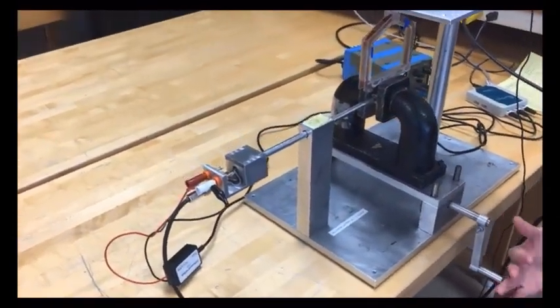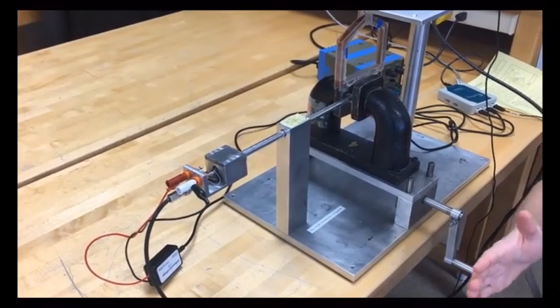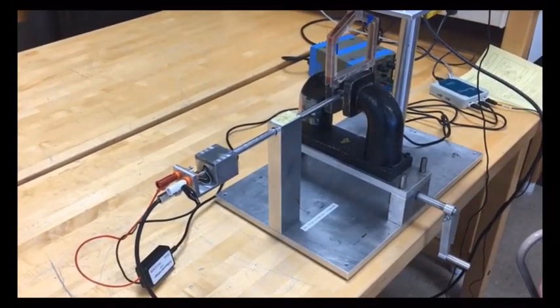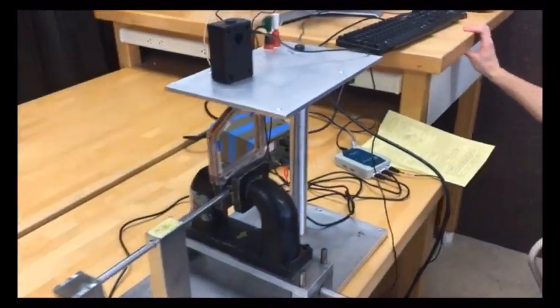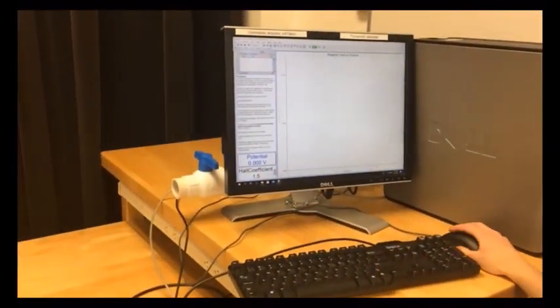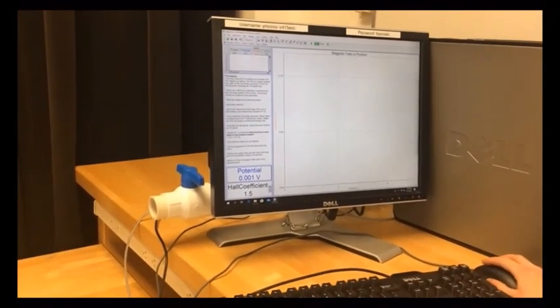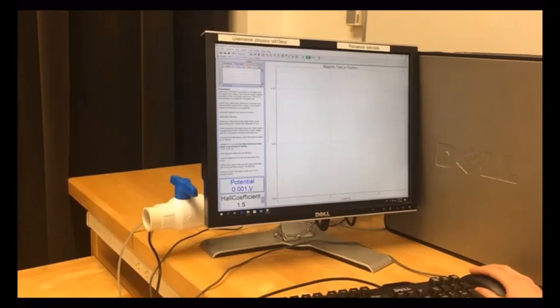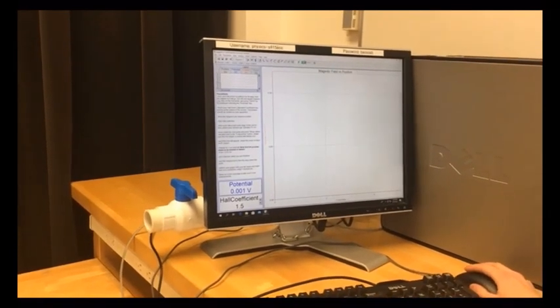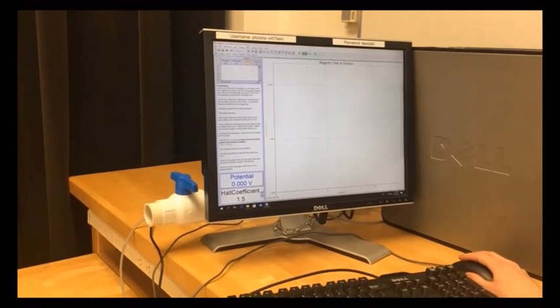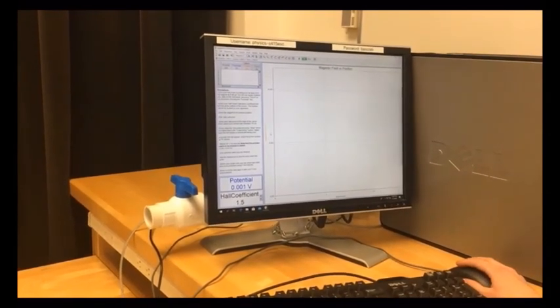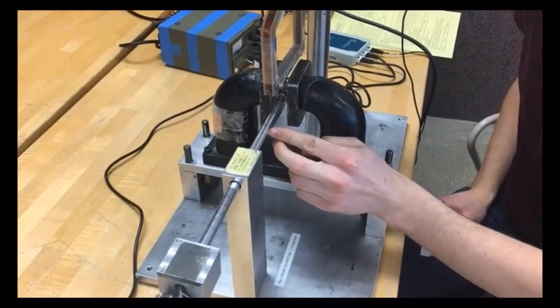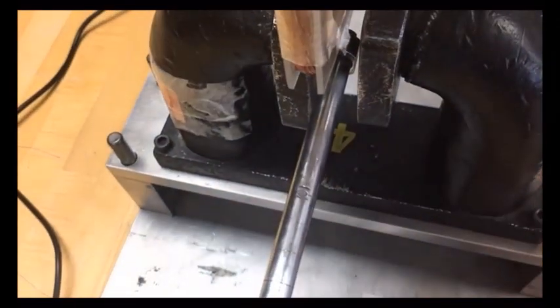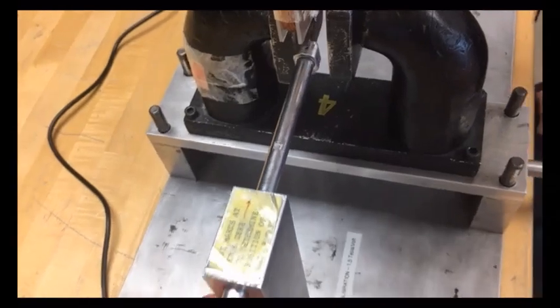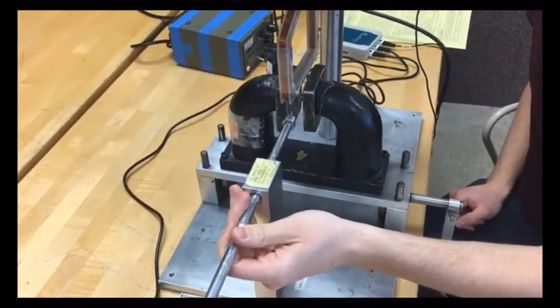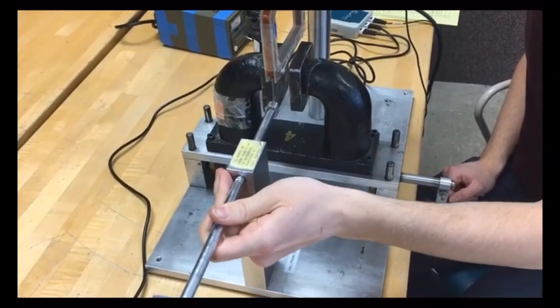But if we multiply it by 1.5, we can take that voltage and convert it to Tesla. And we're actually going to do that automatically on the computer. So this is a software file that we're going to be using. We set this Hall coefficient to 1.5 so that whenever we take a measurement, it'll just automatically adjust it so that we're plotting the Teslas, the magnetic field, instead of a voltage. The nice thing is that there are little tick marks on the Hall probe here that are each spaced 1 centimeter. And so we're just going to start at 0 centimeters and then go to 1, 2, 3 centimeters, and then that's how we're going to plot the position.